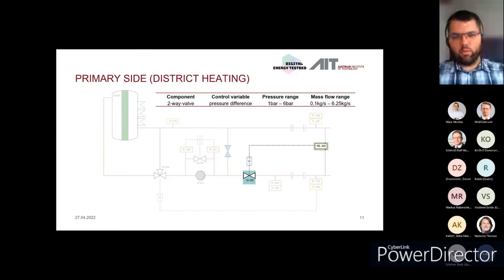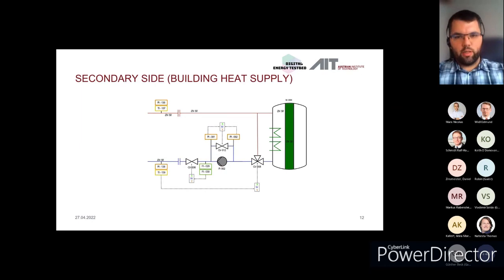So this was overall the primary side with the most important components. We also have a pump, but it runs at a constant rotation speed, so we do not really control it at this stage. For the tests we'll see afterwards, we have a constant flow temperature and constant pressure difference set there. This isn't controlled by our model, but our model controls and communicates with the secondary side, which represents the building in the end.